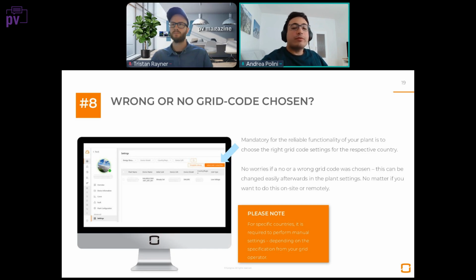So we have seen several issues of customers selecting the wrong grid code during commissioning. And the good news is that it's possible to change the grid code afterwards. So anytime, remotely, if the installation is online, you can just go to the settings menu, and the first setting that you have on the right is this initial grid connection.